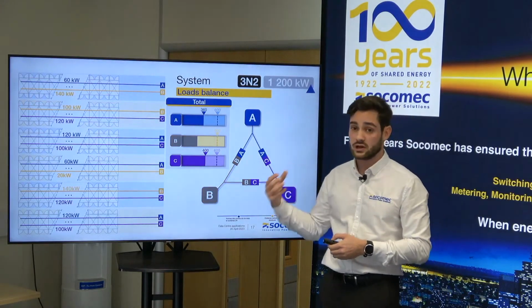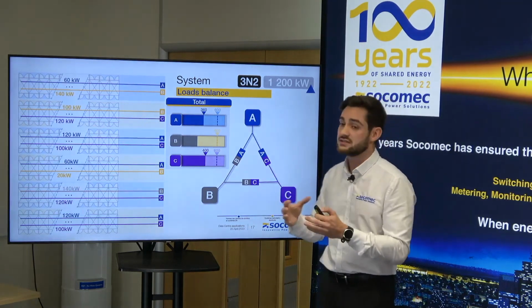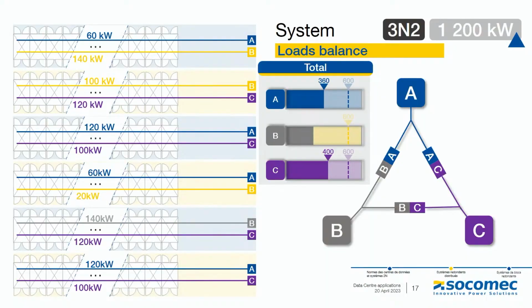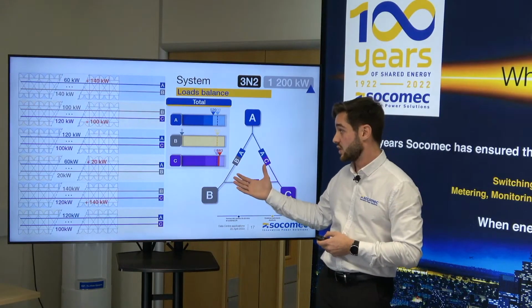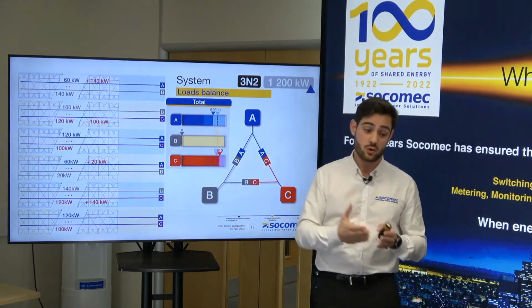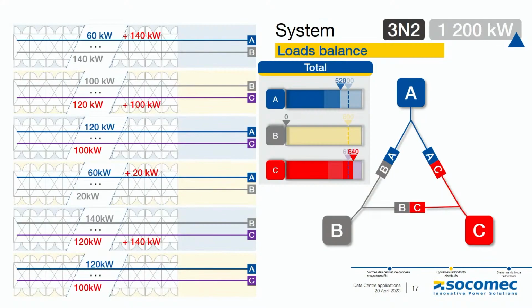But if it's not done the right way, imagine you're oversized on one system and didn't take into consideration the downgraded mode. What could happen is, when you lose a power path, in that specific example UPS system B, then the other UPS systems will kick in, and they will need to take this load from UPS system B. But if it's not balanced properly across the 3 different systems, the result can be overloading another UPS system, and then we will go through the overload capability and the UPS system will probably shut down. And then the risk, of course, is to lose this UPS system as well, and losing 2 power paths and then dropping the load.